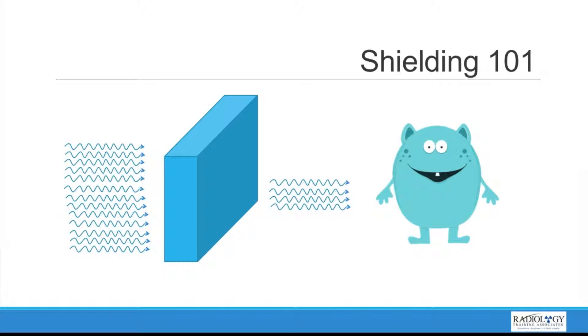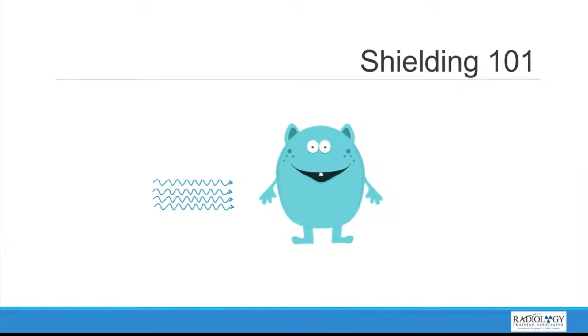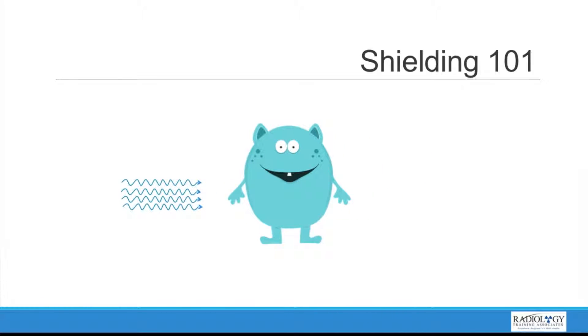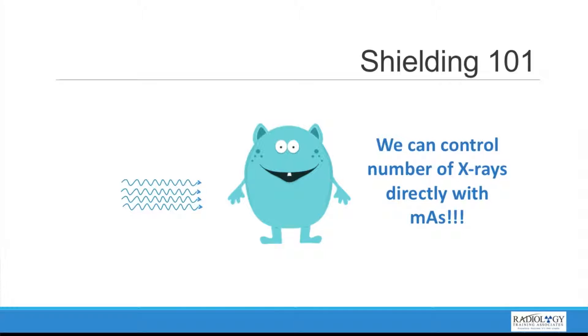However, there's a separate control for this already built into a CT scanner called mAs. The mAs is a relationship of the number of x-rays impacting the patient. So instead of using a shield which decreases the number of x-rays hitting the patient, we can do that directly through the mAs, which also decreases the number of x-rays entering the patient.